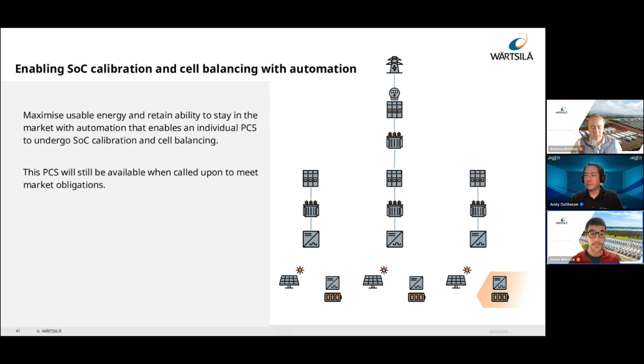If we think about that stool I showed before, with the BMS, the PPC, and the battery analytics, that integration is important for this. The BMS needs to do the calibration. The PPC decides which inverters go down and moves the power or energy levels down to a point where the calibration can take place. The battery analytics helps by thinking, is it a rock star pupil or a problem child? How often should I do these calibrations? This is where that integrated solution is quite valuable.